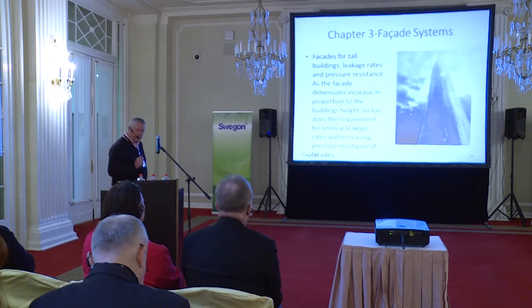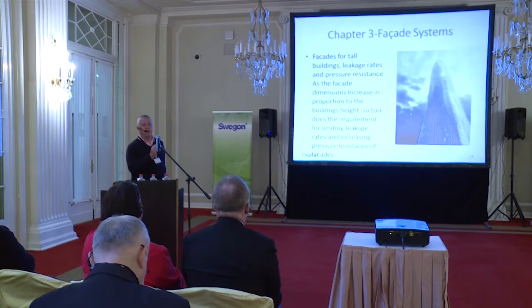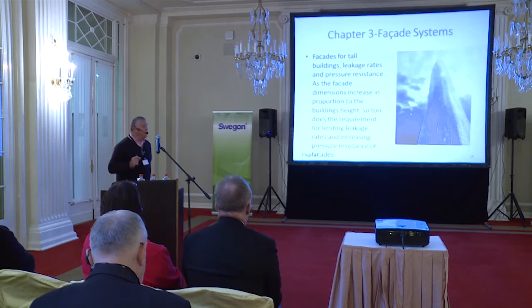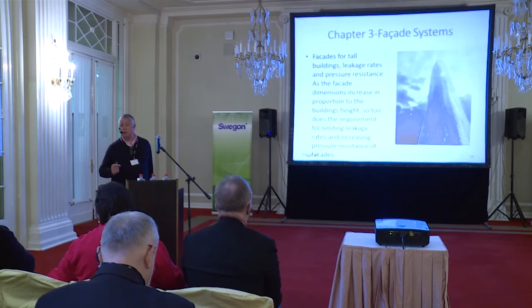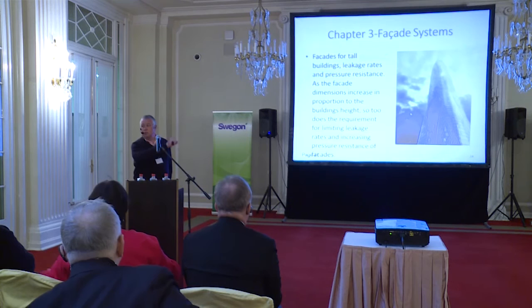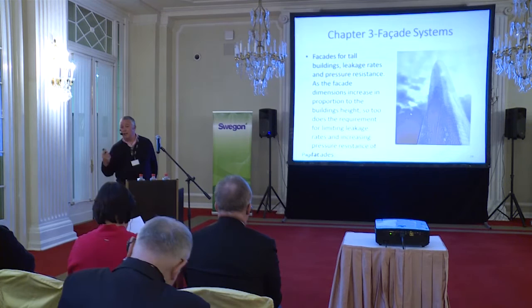One of the other points is when we get higher up a building, we're seeing it in the weather data, that the wind velocity increases. So if you start looking at what the possible leakage rate could be for a building, when you go up, you've got a higher pressure. So how do you allow for that in your building? As engineers, if we have infiltration, and like where we are, February in St. Petersburg, that air temperature is going to be very cold. So if we have twice as much infiltration due to the higher air pressure and wind velocity, how do we account for that back in our load calculations, which comes back to the size of equipment we need for our buildings?